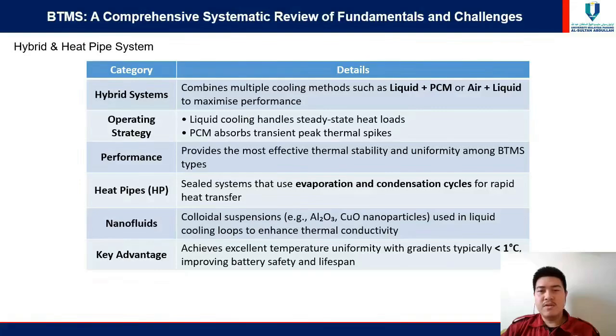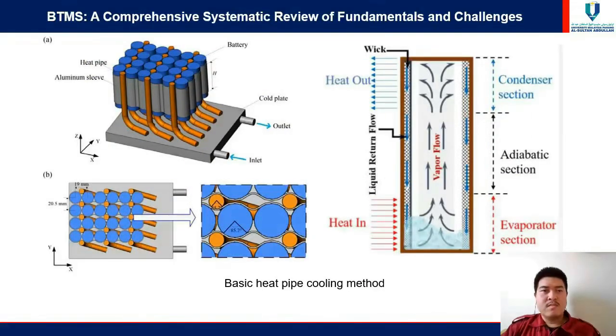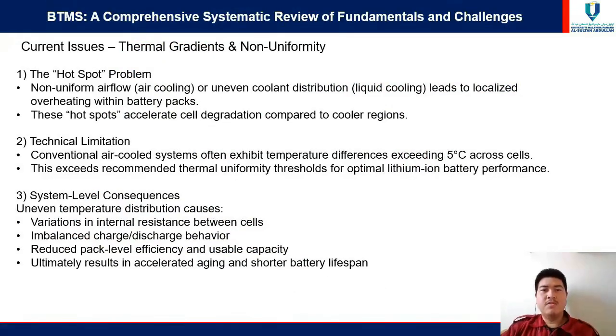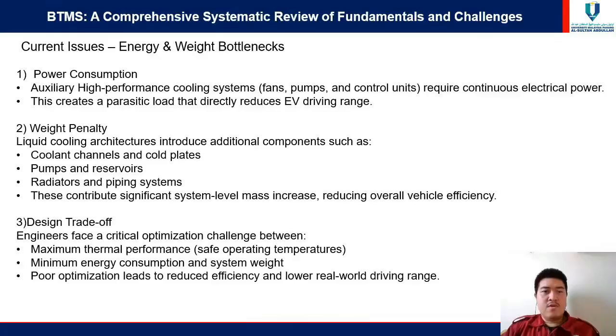achieving gradients below 1 degree Celsius. As you can see in this picture, this is a basic heat pipe cooling system method. Despite this technology, we still face the hotspot problem. Non-uniform airflow or cooling distribution leads to localized overheating, which accelerates cell degradation and reduces the usable capacity of the entire pack. For engineering and weight, we also face energy and weight bottlenecks.